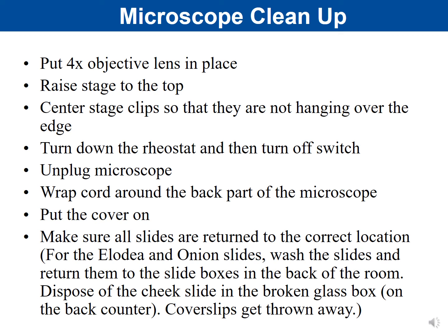Now there is some debate. Some people raise it, some people lower it. For the purpose of this, we would raise it to the top. We would center those stage clips. So those metal parts that hold the slide, we would want to center those so that they're not hanging over one end. Because if they're off to one side and you happen to hit them, you might break it. So we want to make sure that the stage clips are in the middle and not hanging over one side or the other.